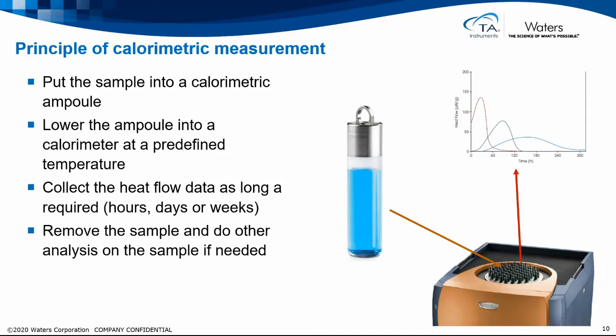It's simple to do calorimetry. So the principle of a measurement is that you put your sample in a calorimetric ampule. We see here a blue sample in an ampule. You lower the ampule into the calorimeter at the predefined temperature, and you collect heat flow data as long as required: hours, days, or even weeks. When you're finished, you remove the sample and can do other analysis of the sample if needed.